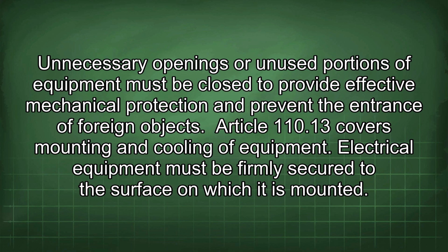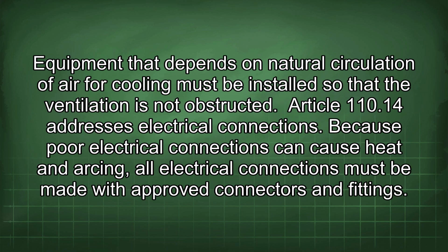foreign objects. Article 110.13 covers mounting and cooling of equipment. Electrical equipment must be firmly secured to the surface on which it is mounted. Equipment that depends on natural circulation of air for cooling must be installed so that the ventilation is not obstructed. Article 110.14 addresses electrical connections. Because poor electrical connections can cause heat and arcing, all electrical connections must be made with approved connectors and fittings.